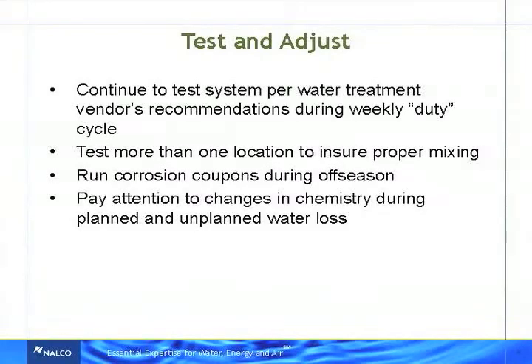Pay attention to changes in chemistry during planned and unplanned water loss. Now, planned water loss would be chiller maintenance. You're going to take a bundle down, so you're going to drain it and then refill it. Cooling tower cleanings, when you're going to drain your cooling tower. Maybe you're going to add a piece of equipment, so you're going to have to drain a section, a couple headers or something like that. You're going to do a hot tap, so you can lose some water out of there. Those are planned water losses.